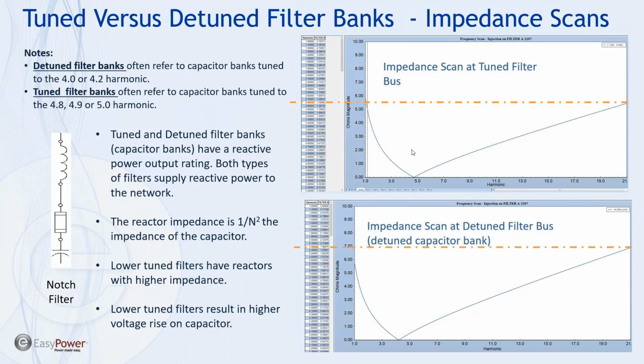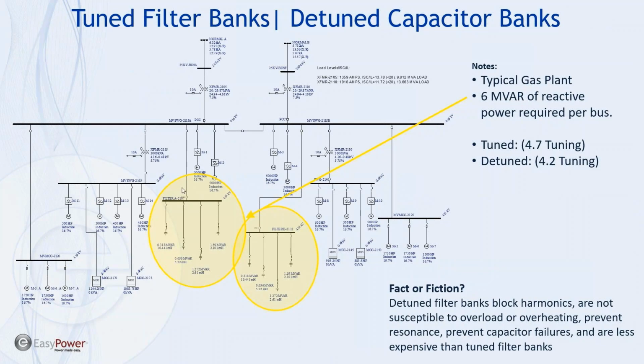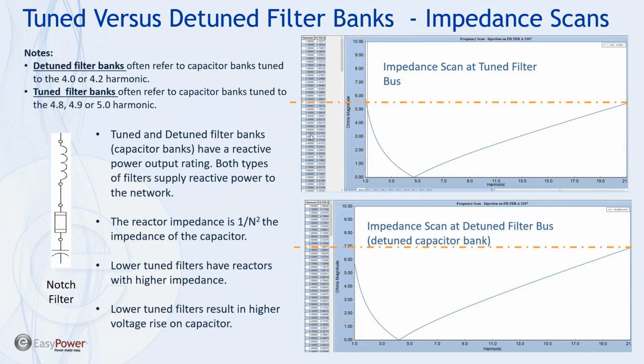So you might ask, well, how did I get this curve? I think it's worth mentioning, since this is an EasyPower webinar, that after you go into harmonics mode, you open the switch at the filter and you double click the bus. I have set the system up under harmonic options such that we're using a 1 amp injection, and I set the plot up so it plots ohms, and then that way we have a plot of impedance. You can pull the window over in EasyPower and come up with the actual value of ohms here at each frequency. Okay, so if you study the curves here, we both have a scale of 10 ohms. You can see that they are only slightly different in value.